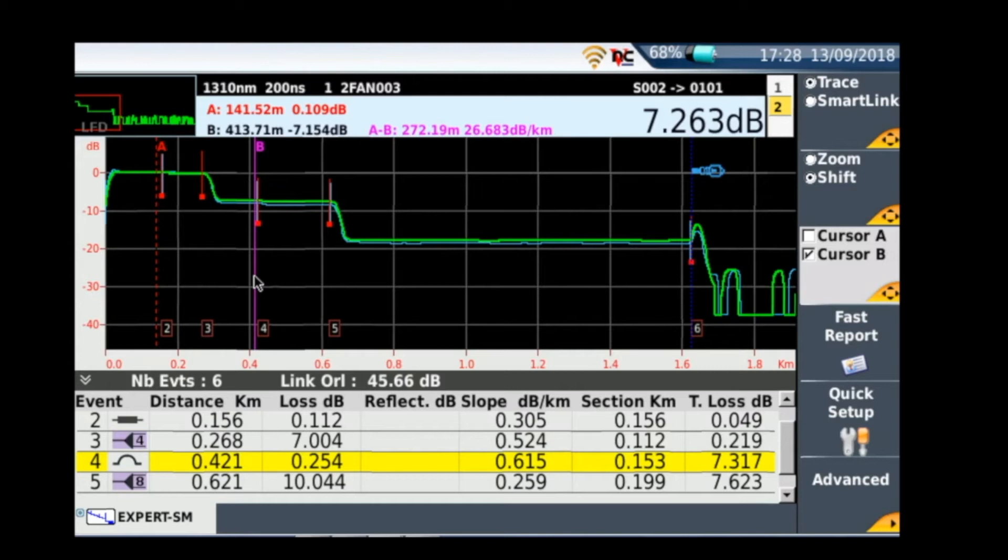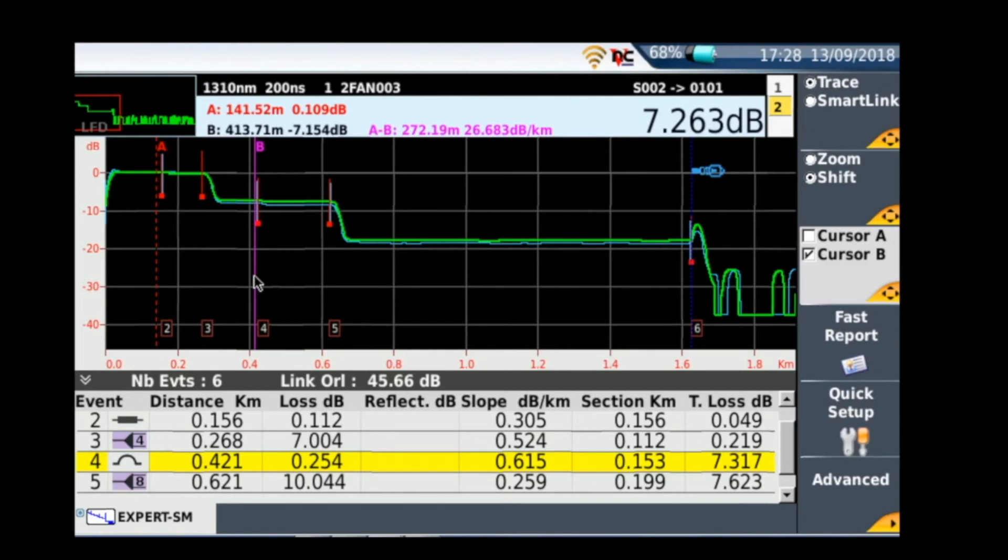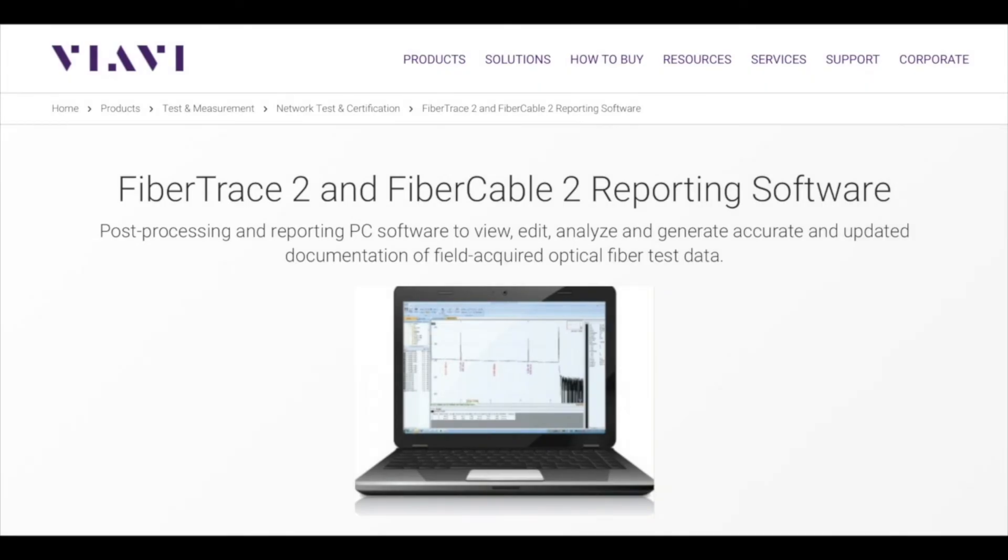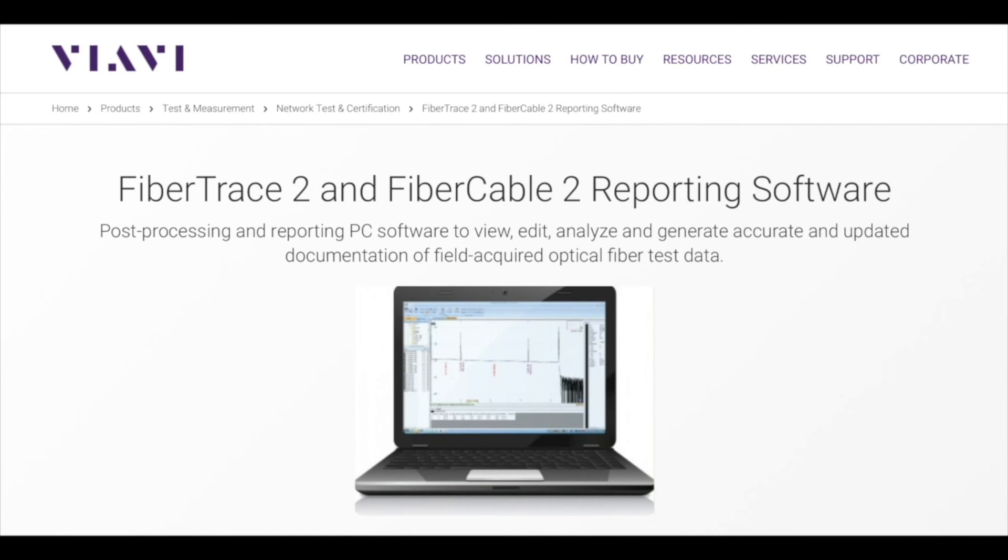Okay, another option you have is if you're out in the field and you've got lots of traces to take and you really don't want to be spending your time out in the field changing your cursors and saving your results from there, you can save your results as normal and then use a software such as FiberTrace 2 and FiberCable 2 at a later stage, maybe later that evening. And with this software you can then move your cursors and save the results. FiberTrace 2 is a free software from VIAVI and you can easily find that to download from their website. FiberCable 2 is a licensed paid software, but it really speeds up the process if you're testing on the DFN network and it also will allow you to upload into the NBN workbook for DFN work. And we'll cover that off in a future video.